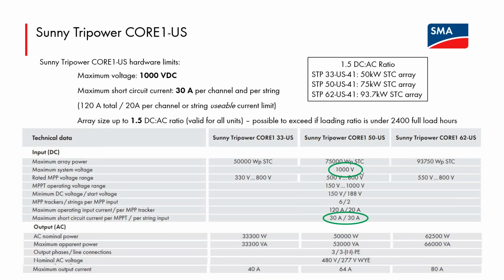So these 2 values circled in green are the ones SMA cares about. If you exceed these, technically you're voiding the warranty of the device. So these are the limits that we at SMA care about in terms of hardware. In operation, the inverter will pull a maximum of 20 amps from each of the 6 tracking channels. So that's kind of the limit the inverter will safely hold at in operation. The short circuit current limit, that's obviously a design limit, and we care very much about this, and the 1000-volt limit.